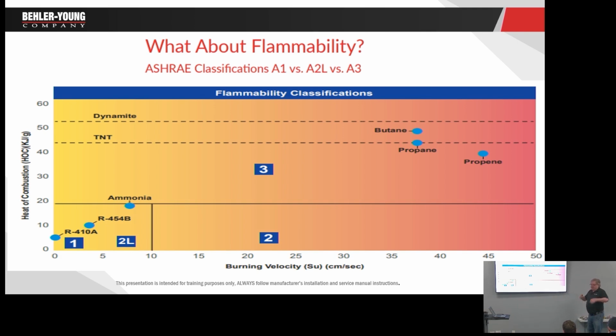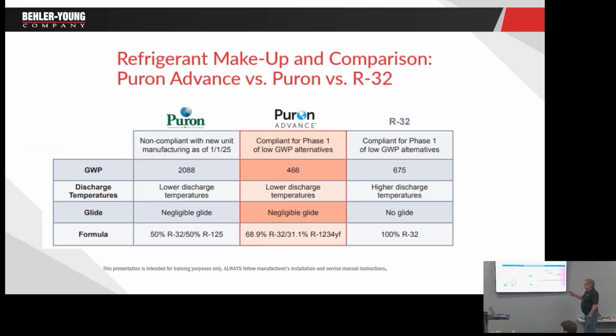So it's nothing to be afraid of. We do need to be cognizant of the fact that it is technically flammable, but it's really hard to ignite. I would suggest you Google A2L flame spread test, and you will find five or six videos there of guys actually trying to light it, and you'll see what I mean. So it's not like we should be afraid of it. We need to be a little respectful because they've gone through all this, and it is flammable, but again, it's barely flammable.